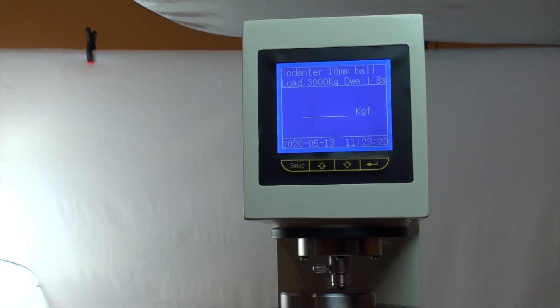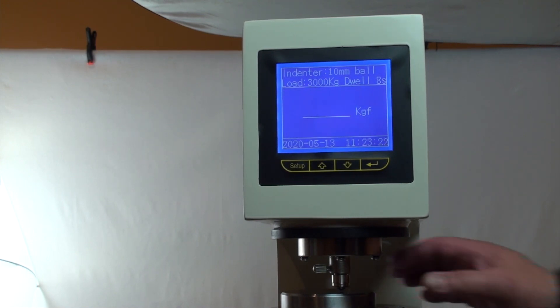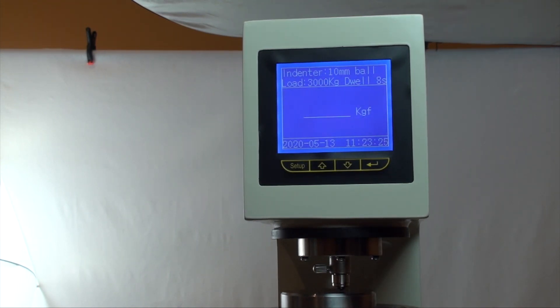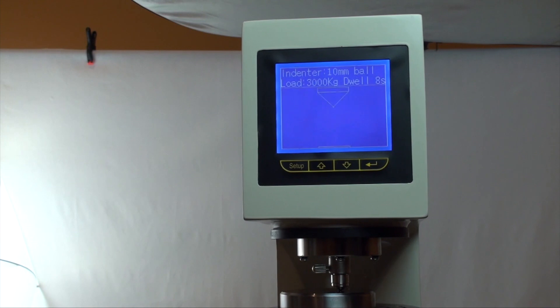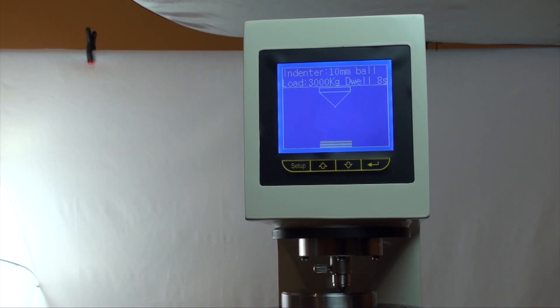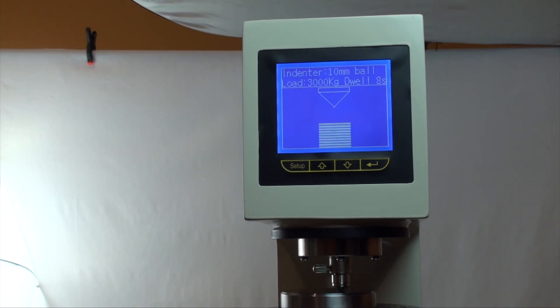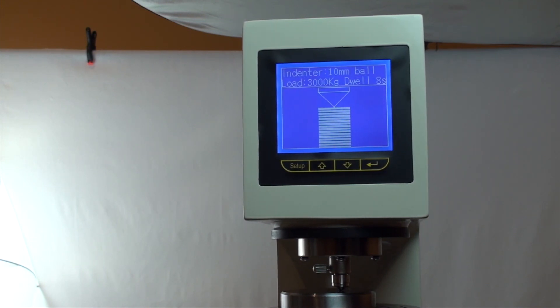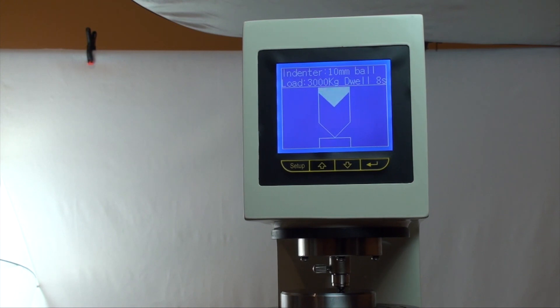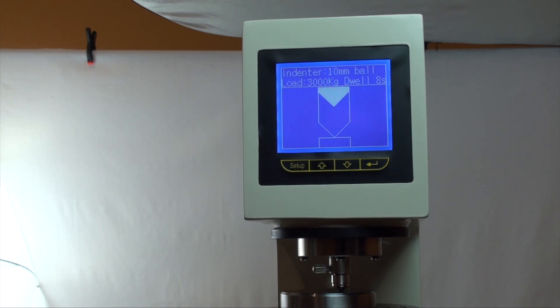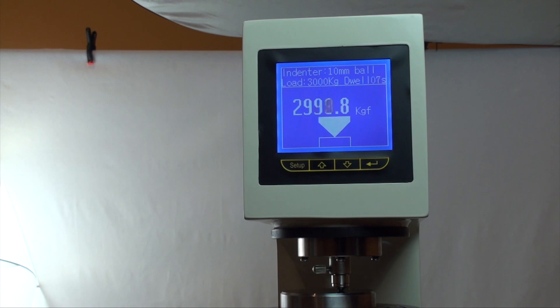Taking a test is as simple as fixing your test block on the anvil. Bring up the test piece by turning the collar clockwise until the screen shows contact and the beep sounds. The tester will finish loading, dwell, and then unload on its own. Once this part is completed, the screen will show the weight load being used.